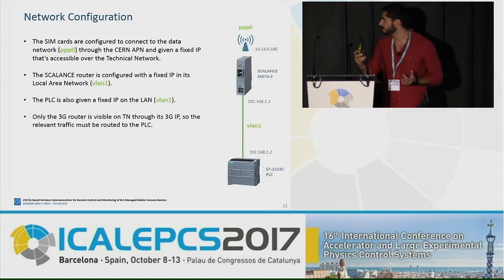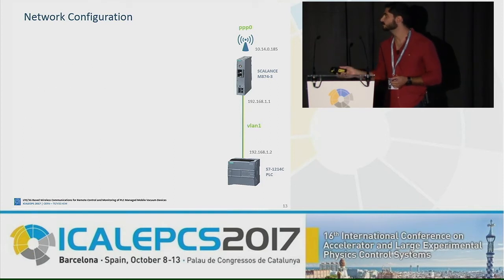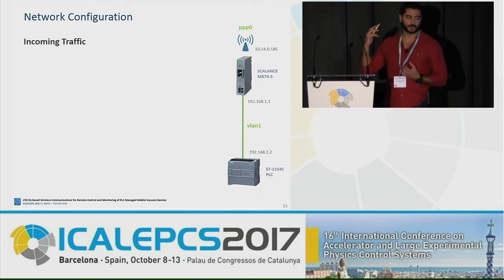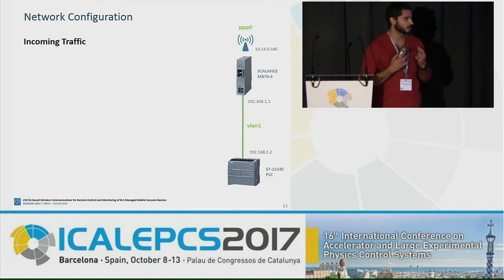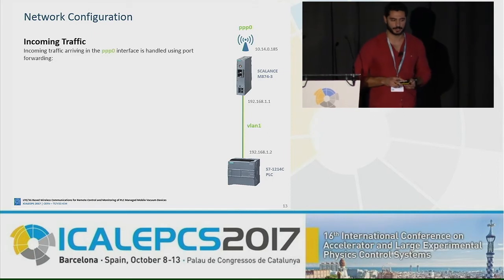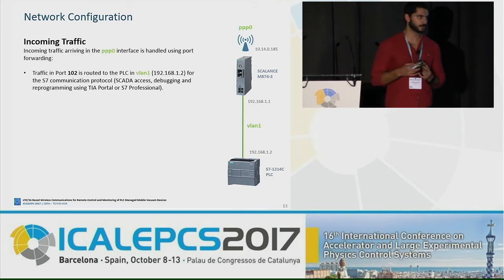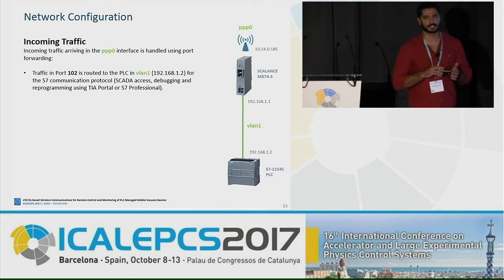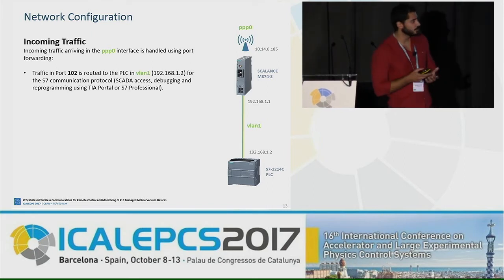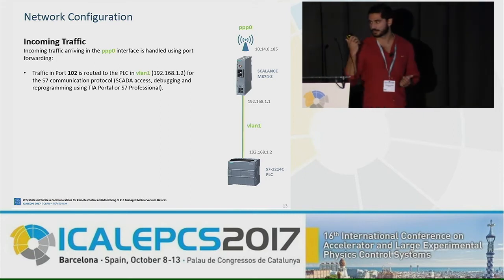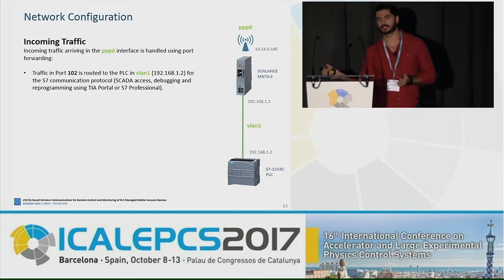Here's a summary: we have a fixed IP on our technical network, a local network for the PLC, and we need to reach this PLC. For incoming traffic, we route 2 particular ports to the PLC. Port 102, the port used by Siemens Step 7 communication, is routed to the IP of the PLC. This means that with the IP of the SIM card, we can connect directly to the PLC.